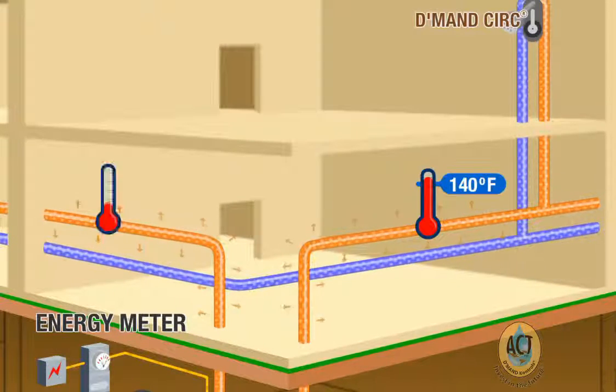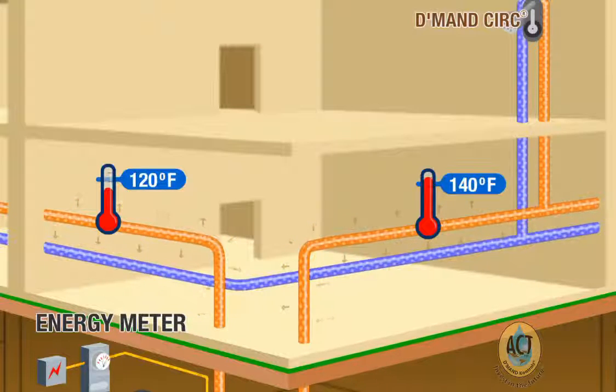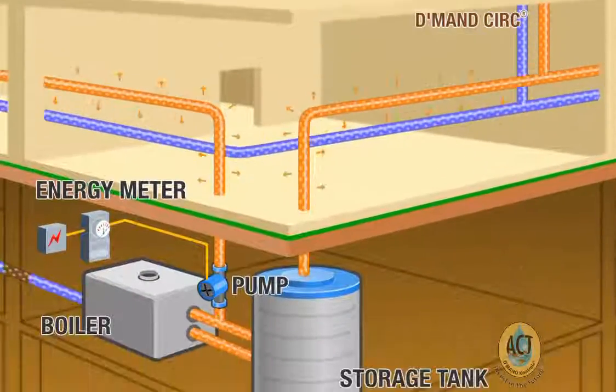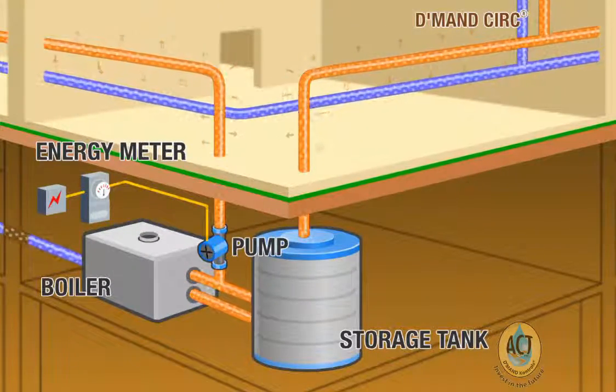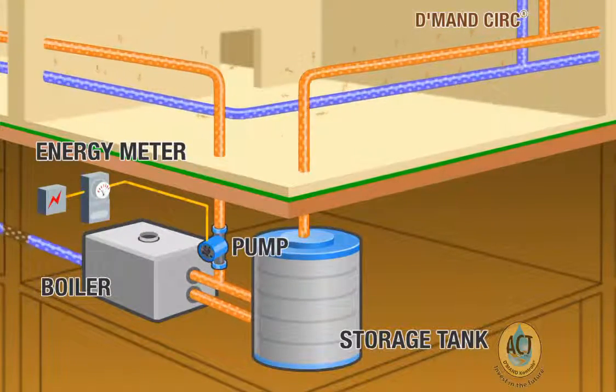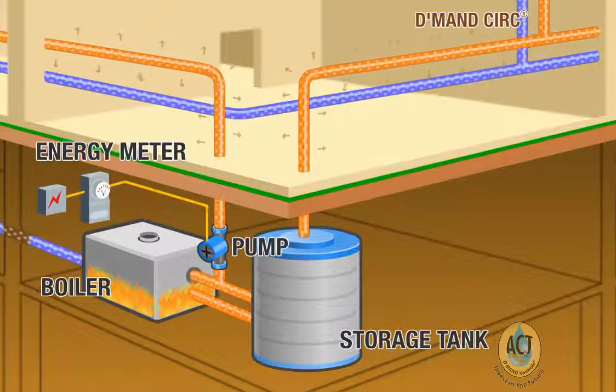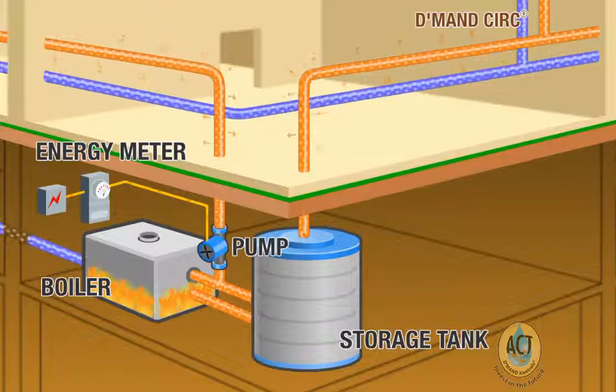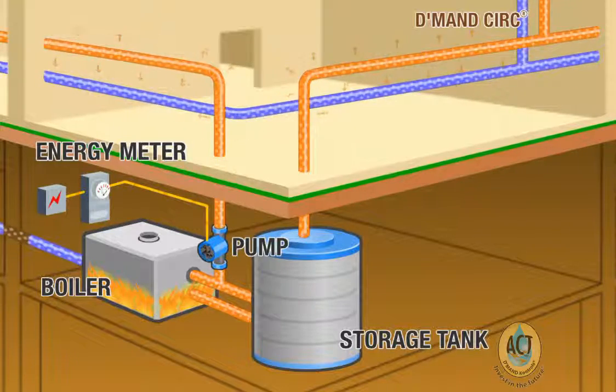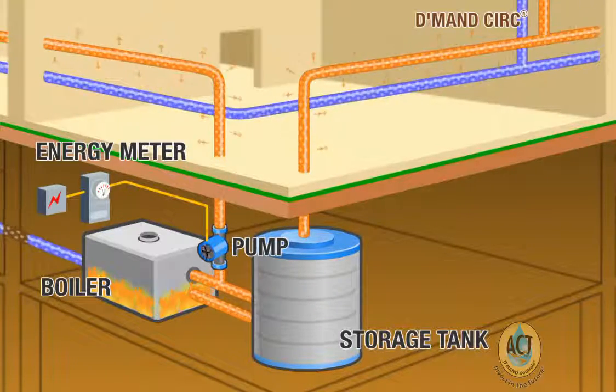By the time the water has circulated back to the storage tank, it is often much cooler than it was when it left, and this cooler water is being dumped back into the storage tank constantly, whether or not occupants are actually using hot water. This loss in heat must then be made up by the boiler or water heater, resulting in excessive gas or electricity consumption.